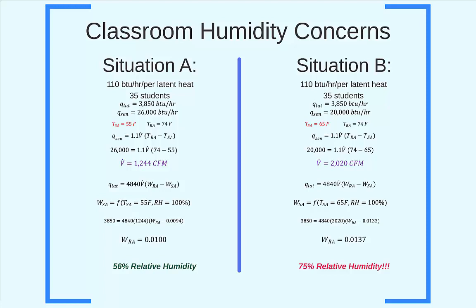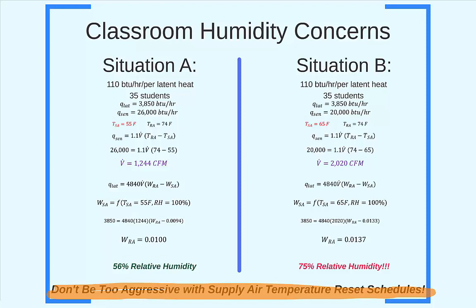So what is the moral of the story here? In humid climates, don't get too aggressive with your supply temperature reset schedules. It is never advised to bring the set point any higher than 60 degrees Fahrenheit in humid climates. Otherwise, there will be times when the relative humidity of the space will creep into unacceptable levels. It is recommended that the supply temperature be capped at 65 degrees Fahrenheit in drier climates, as space humidity is not as big of a concern.